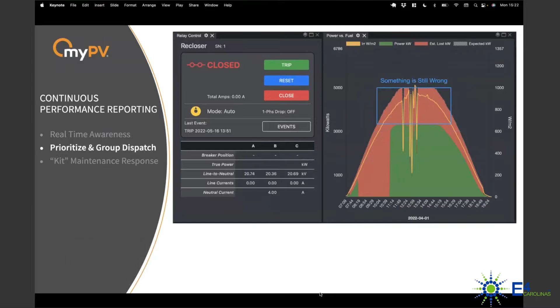We're still missing some energy, some power production on site. Looking at a few other pieces of information available to us, we're looking at the 3 inverters on site as they operated during the day. They started up, and then we had our recloser trip event, and all 3 inverters came offline, and the entire site was offline.